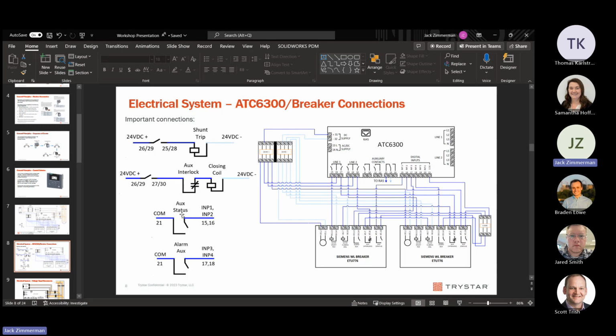And then of course we have the auxiliary status and alarm auxiliary. Alarm auxiliary is just the trip indication I talked about. This is the way it's wired in. So effectively, you have some kind of relay on your breaker. These are located on the top of the breaker in those big I/O modules, up by where we do ERMS, the COM35 module. What we're doing is bringing a common port from a PLC relay output, so some kind of power from the controller. In this case, I chose 3.3 volt DC. And we're going through this switch. If the switch is closed, that means it senses it at this digital input, and so we know there's a trip. So that's how it detects the trip condition of each breaker through the bell alarm.